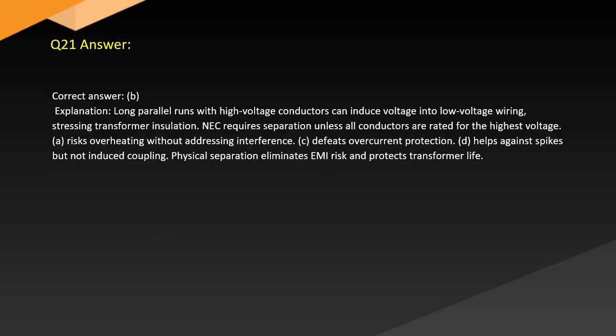Answer. Correct answer: B. Explanation: Long parallel runs with high-voltage conductors can induce voltage into low-voltage wiring, stressing transformer insulation. NEC requires separation unless all conductors are rated for the highest voltage. A. Risks overheating without addressing interference. C. Defeats overcurrent protection. D. Helps against spikes but not induced coupling. Physical separation eliminates the risk and protects transformer life.